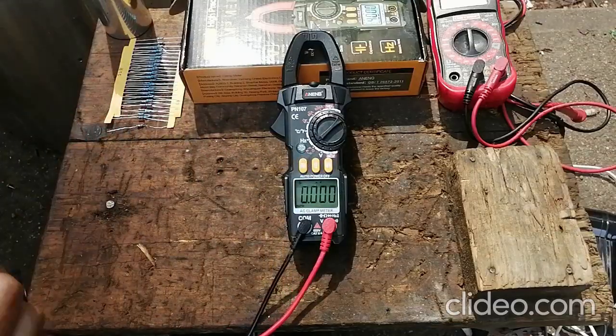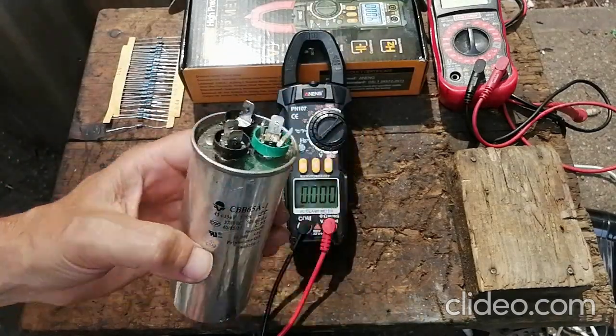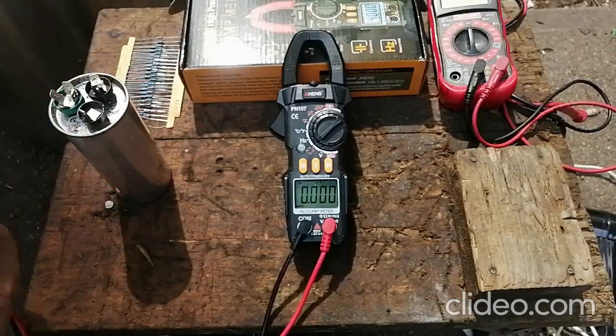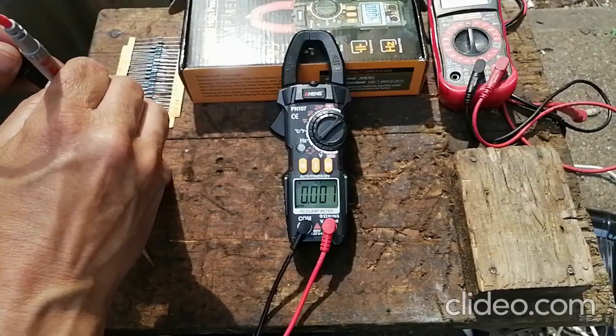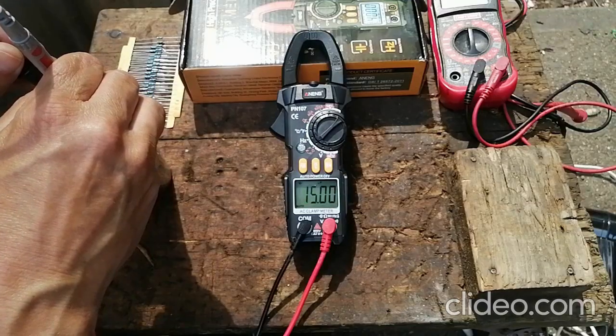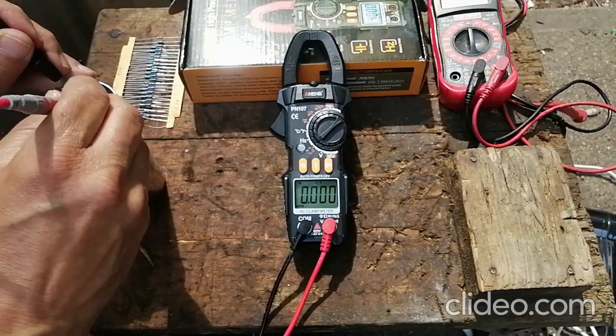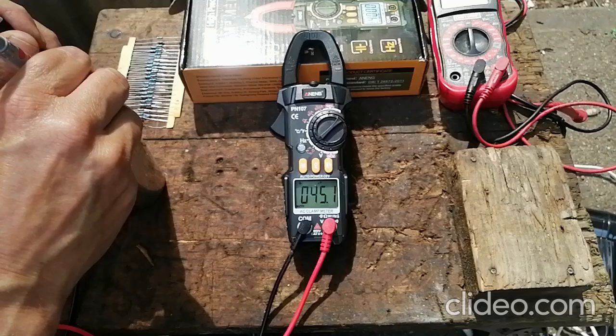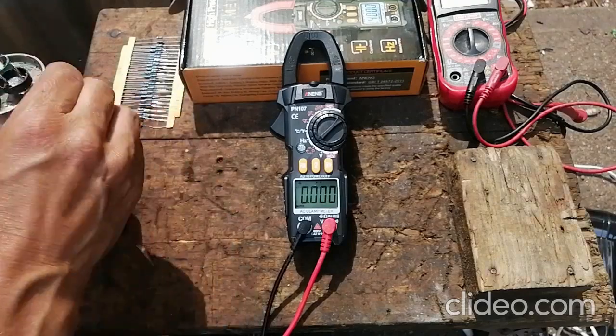I've set it on capacitance now. I have a capacitor rated at 45/15, so let's test it. It reads 15 — right on the money. Testing the other side of the capacitor, it reads 45.1 — almost right on the money. So that's pretty good accuracy.